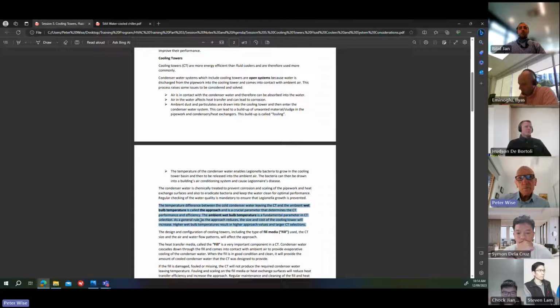As a general rule, as the approach reduces, so the difference between the leaving condenser water and the ambient wet bulb temperature, as that approach reduces, the size and cost of the cooling tower will increase. Higher wet bulb temperatures result in higher approach values and larger cooling tower selections. So if you're in a dry climate, that's good for a cooling tower.